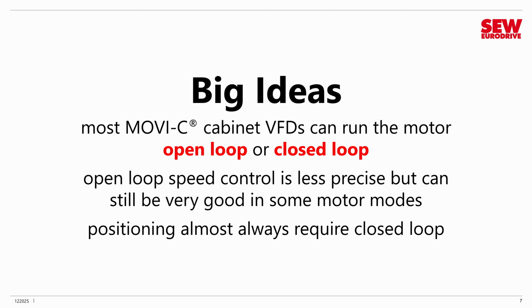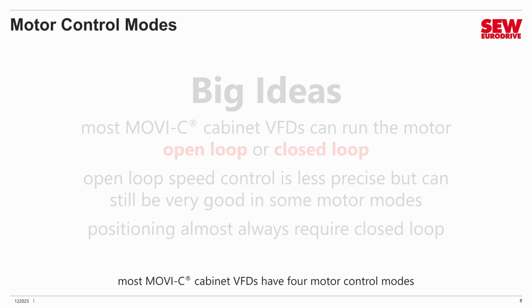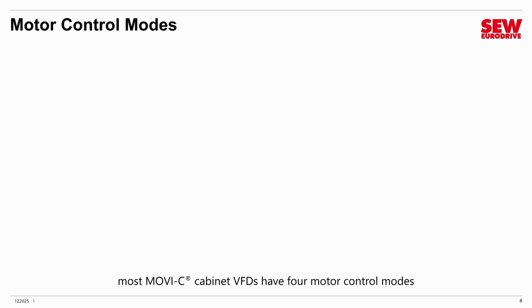Closed loop, though, is better because in closed loop you do have exact information coming back from that feedback device. Now, as a side note, I've said this already, but I'll say it once more. If you're going to do positioning, you almost always need closed loop. Most MOVI-C cabinet VFDs have 4 different motor control modes, and you may wonder, why do we have that many? Well, of course, there are different kinds of motors in different degrees of performance. Let's just summarize the 4 modes very quickly.